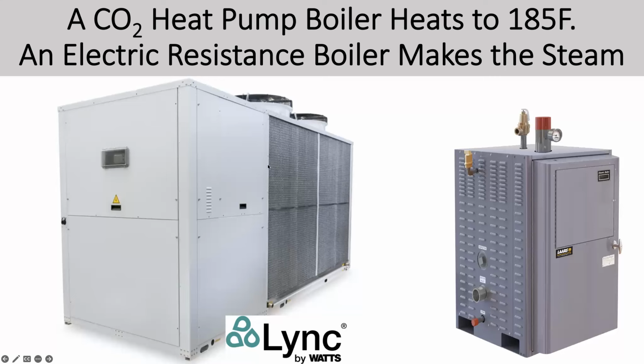One lift happens with the Lync by Watts, made in upstate New York. It's one of many CO2 heat pumps, but it's our biggest one in the United States — 500,000 BTUs. Then that hot water at 185 goes into a steam boiler. That last step isn't efficient — it's electric resistance, 185 to 212, but it can still be clean grid energy, just not efficient. All the rest of the work up to 185 is super efficient with the CO2 heat pump, at a coefficient of performance of about 3.5. So it's 350% efficient — 1 unit of electricity in collects 3.5 units of heat from the environment.